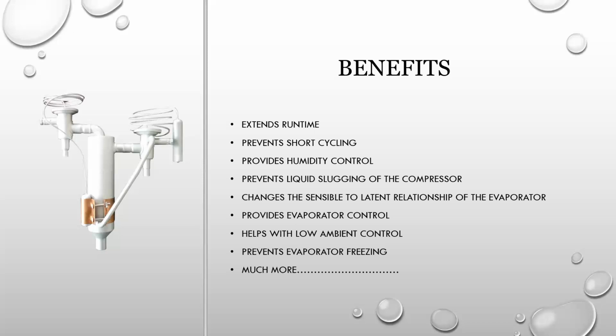Provides evaporator control. Again, this is to control the evaporator and to help out with that. Whereas we have head pressure control for the condenser, this is now evaporator control. Helps out with low ambient. Because it sees a drop in suction pressure and bypasses, you'll eliminate many of your issues with kicking out on low pressure switches. Prevents evaporator freezing. This is because it maintains the evaporator pressure above freezing, or the temperature above freezing, plus much more.